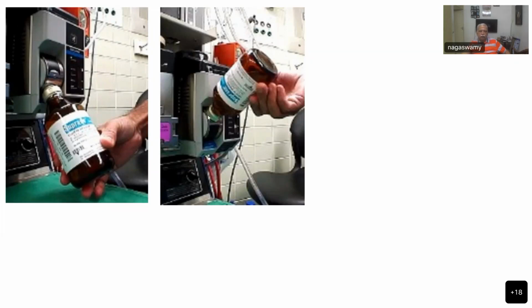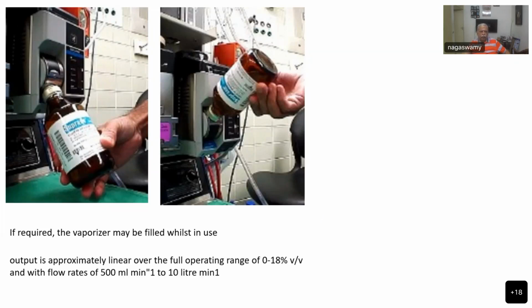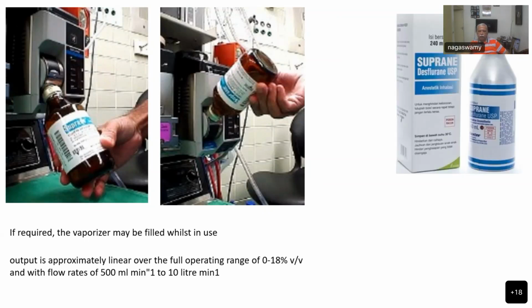Once you tilt that, it gets full, then no more liquid can flow. So that is the mechanism, and it can be refilled while the vaporizer is in use also. And output is approximately linear over the full operating range of 0 to 18% volume, from flow rates of 500 ml to even 10 liters. So whether you use a very low flow or a very high flow, and whether you are operating it at various concentrations, the vaporizer output will be the same. That is a very important beauty of that.